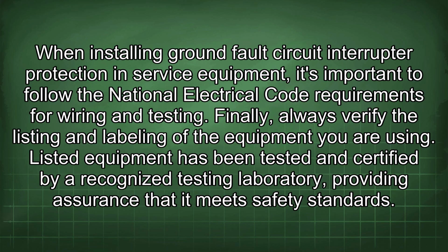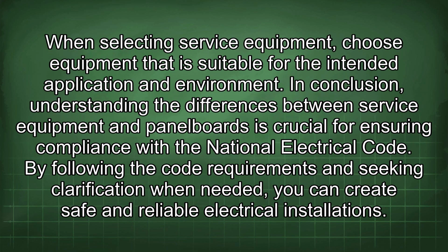When installing ground fault circuit interrupter protection in service equipment, it's important to follow the National Electrical Code requirements for wiring and testing. Finally, always verify the listing and labeling of the equipment you are using. Listed equipment has been tested and certified by a recognized testing laboratory, providing assurance that it meets safety standards. When selecting service equipment, choose equipment that is suitable for the intended application and environment.